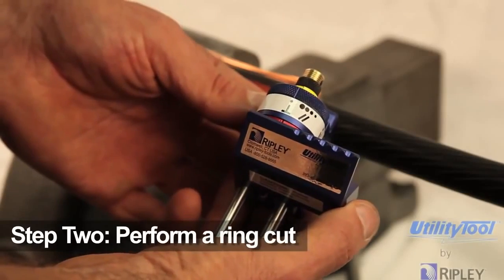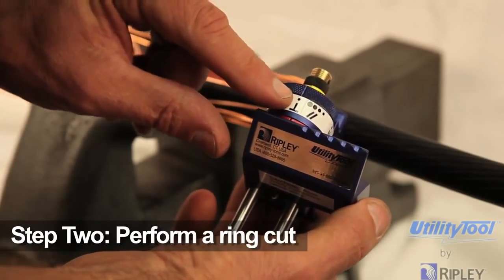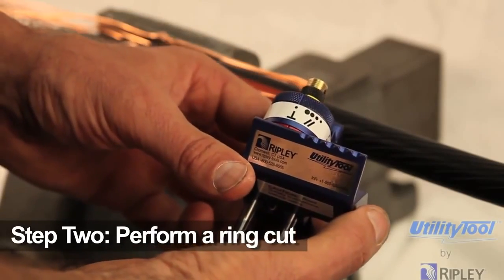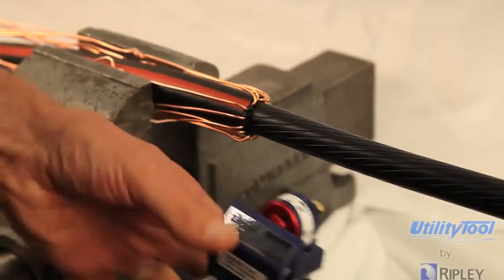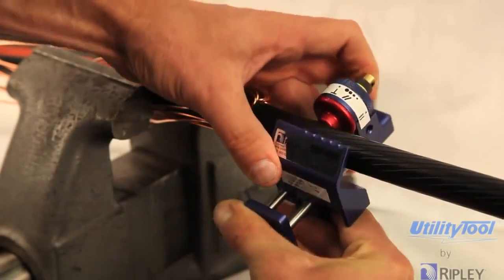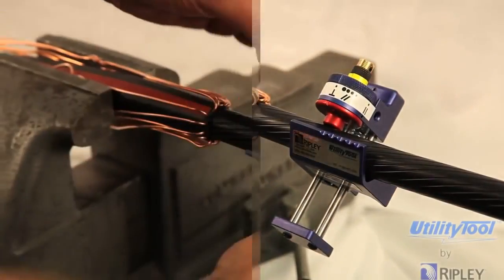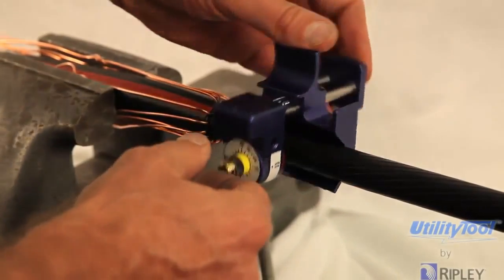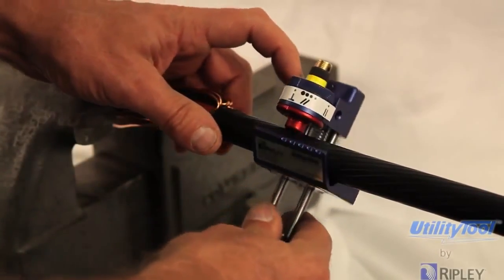Step 2. To perform a ring cut, first observe the blade positioning indicator and ensure it is in the square cut position. Next, lower the jaw to open the tool and secure the tool on the cable at the termination point of the Semicon. Rotate the tool one full turn counterclockwise around the circumference of the cable for a ring cut.